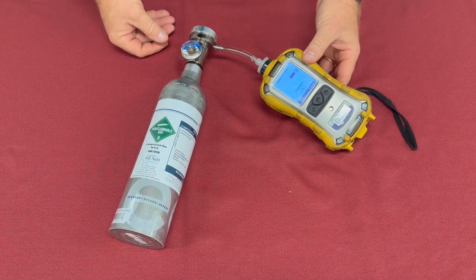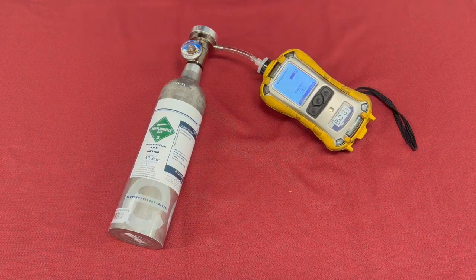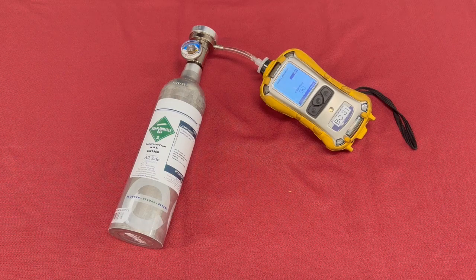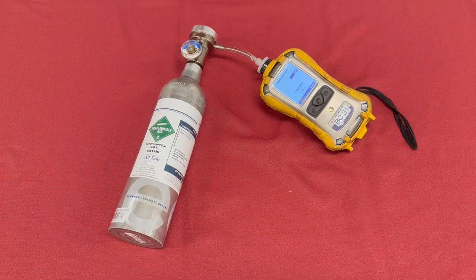Less than 30 seconds to go. We'll be done with this one. The next step, we'll move on to isobutylene here in just a second. When we get to the isobutylene, you'll notice it's in a different color cylinder. Sometimes they're blue and sometimes they're yellow. They're actual steel cylinders instead of the aluminum cylinders because of the nature of the gas, it has to be in a different cylinder.